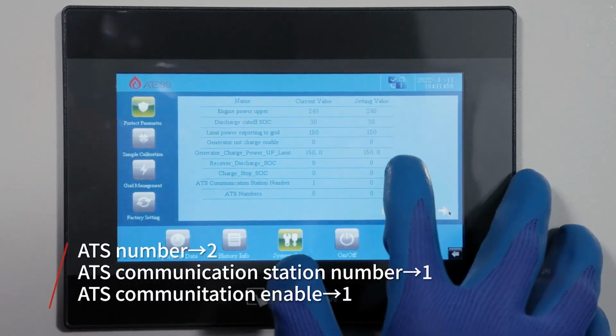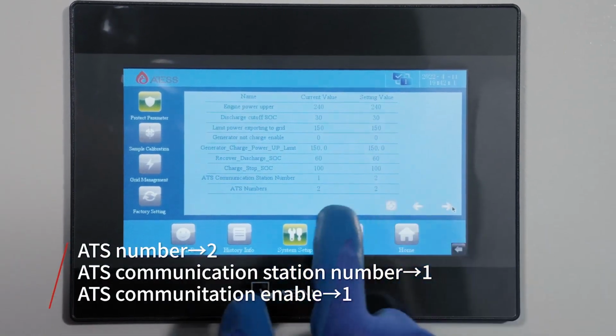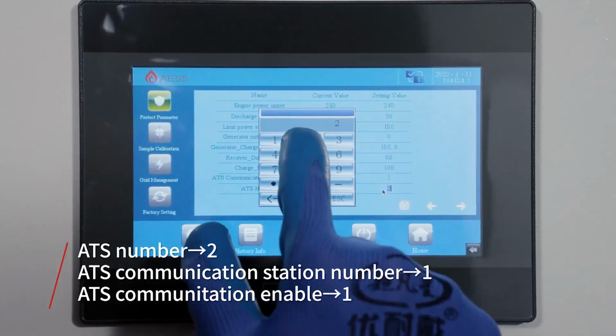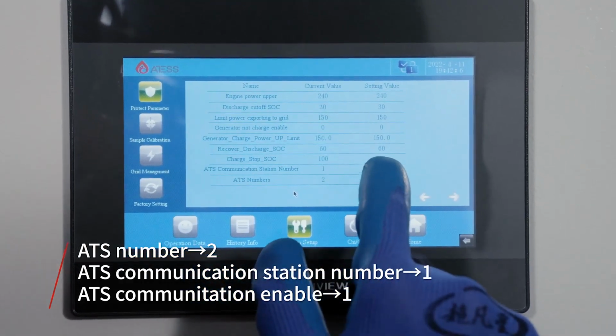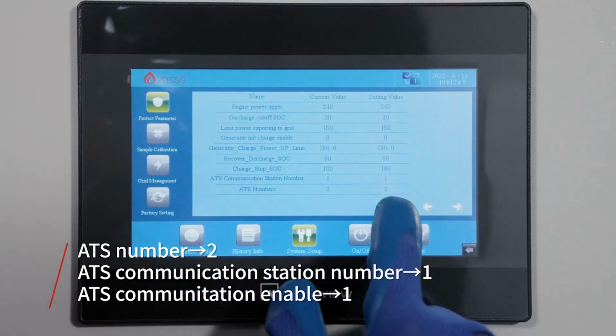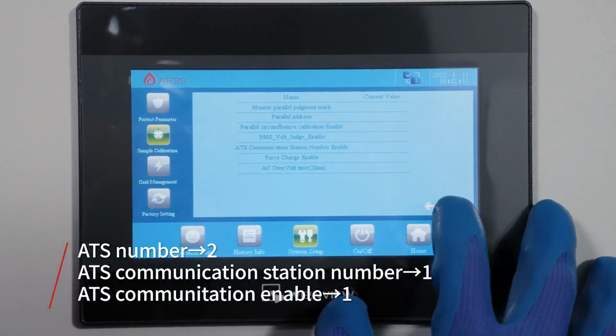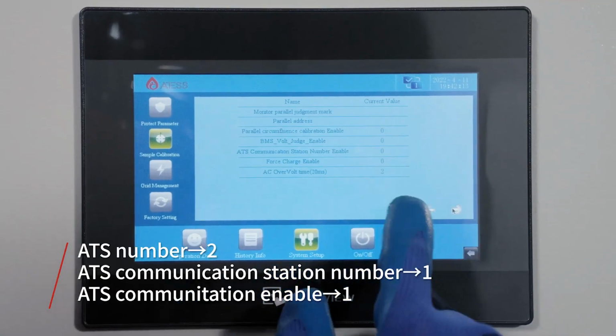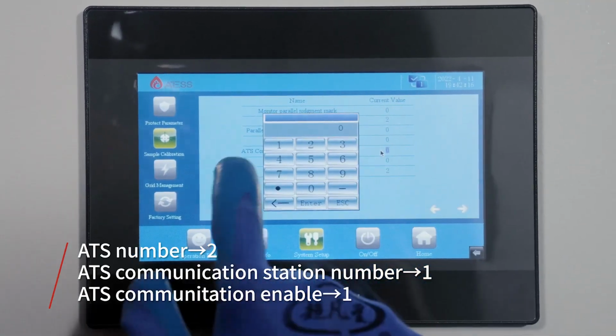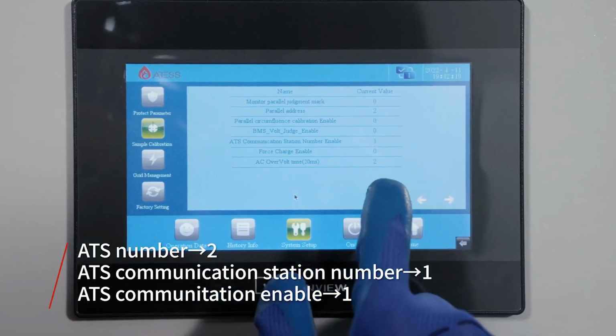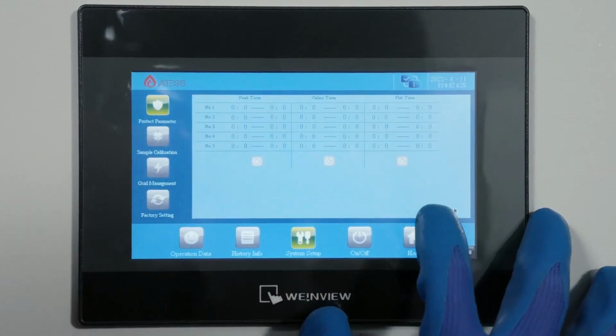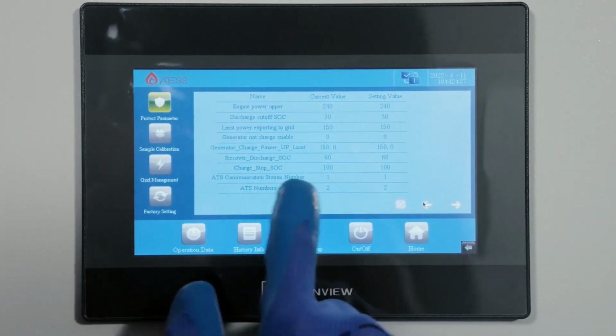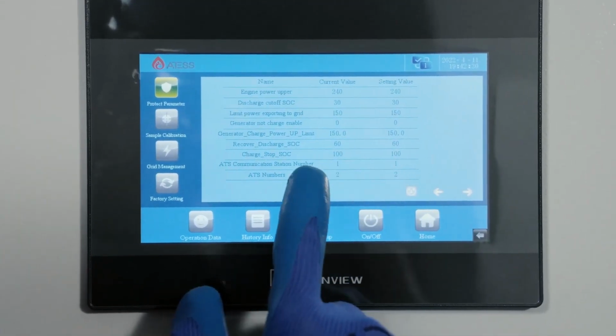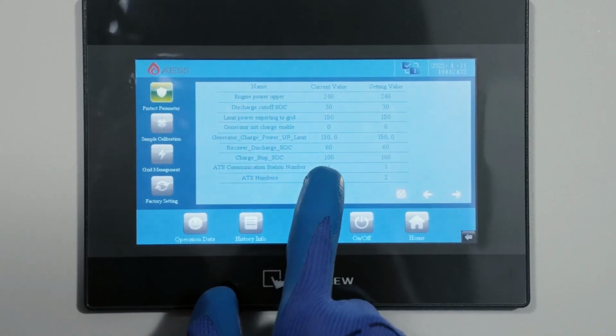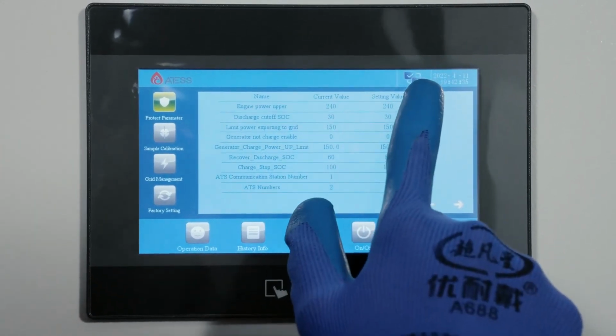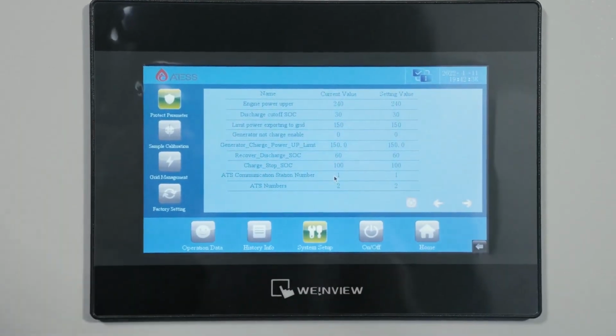Set the number of ATS to 2. Then set the ATS communication station number to 1. Finally, set the ATS communication enable to 1. Return to confirm the number 1 ATS return address. Check whether the current value of the address is 1. If not, deliver the address again or check whether the communication cable is correctly connected.